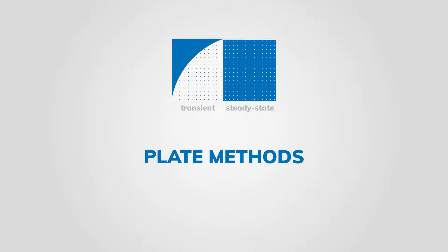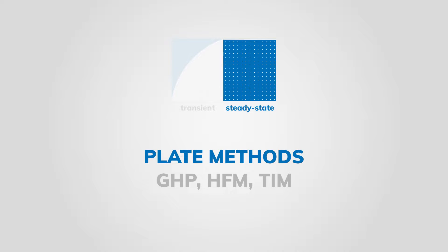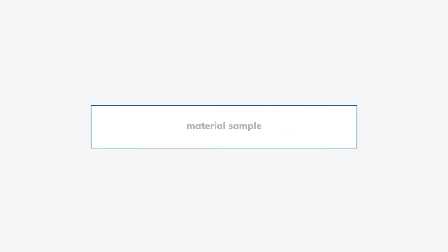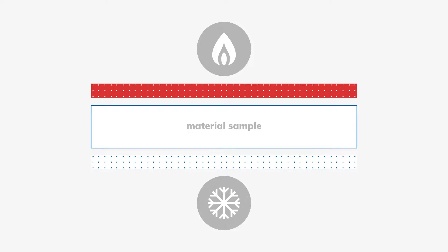Plate methods – such as the guarded hot plate, the heat flow meter, or the thermal interface material tester – belong to the steady-state measurement methods. The material sample is placed between a heated and a cooled plate. This results in a temperature gradient and consequently in a heat flow through the sample, which is monitored until it approaches a constant final value.